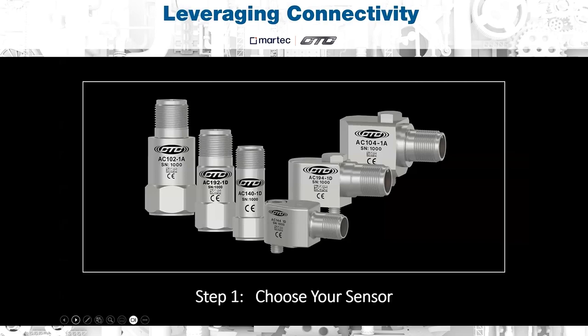So to begin, step one. Matt, just a comment from our side with regards to the enclosures. In a lot of cases, we have some of our customers where just getting accessibility, from a health and safety point of view, either guards or you can't enter a certain area or certain part of the plant from a zoning requirement or a health and safety requirement. So then having the sensors on the equipment and then running the cable out to a termination box allows them to effectively monitor from outside of that zone.